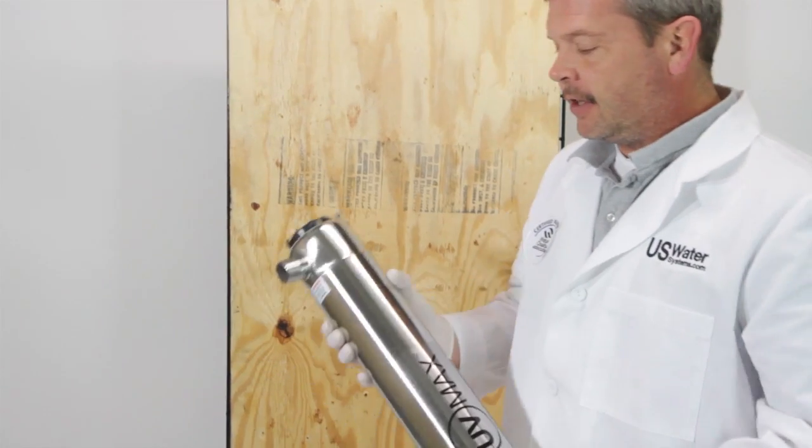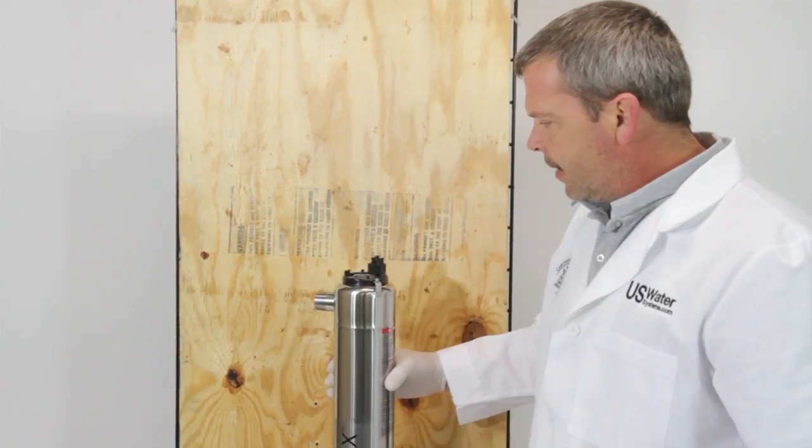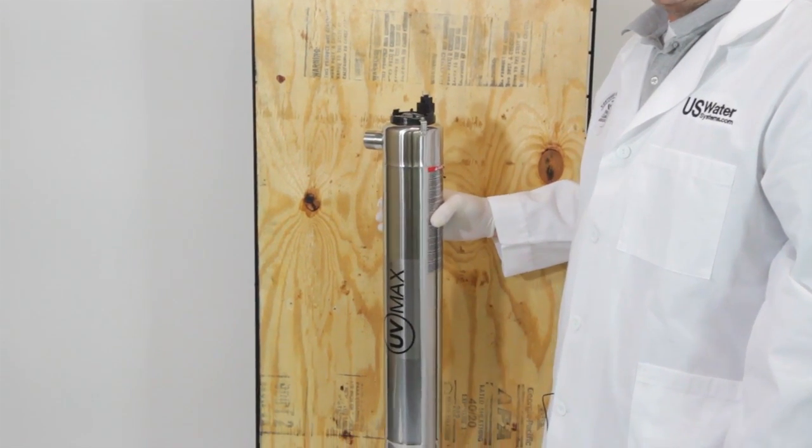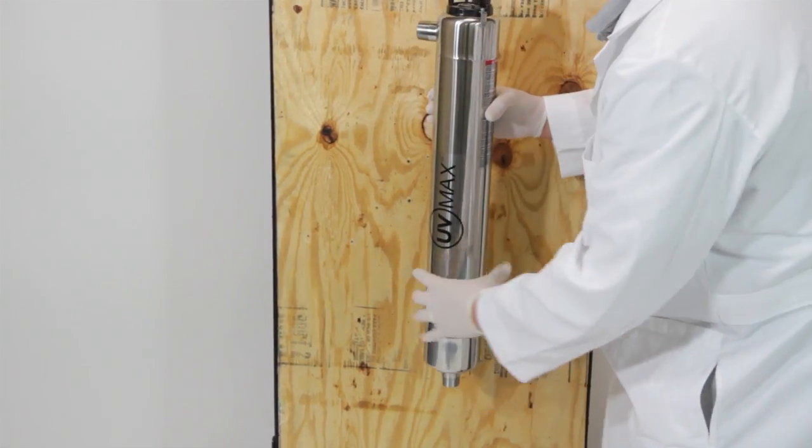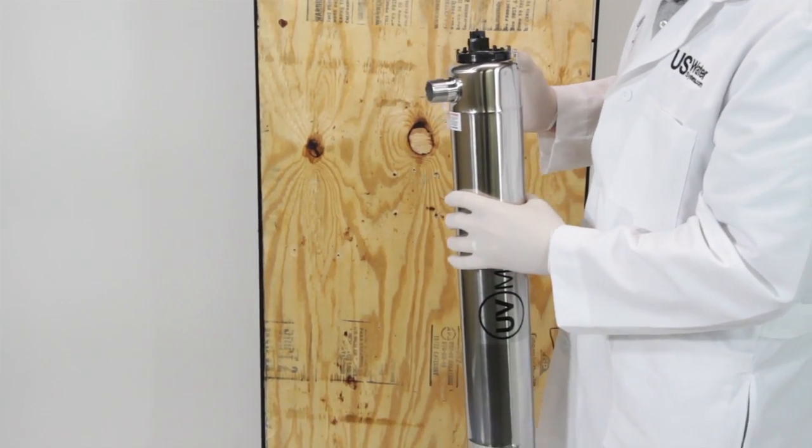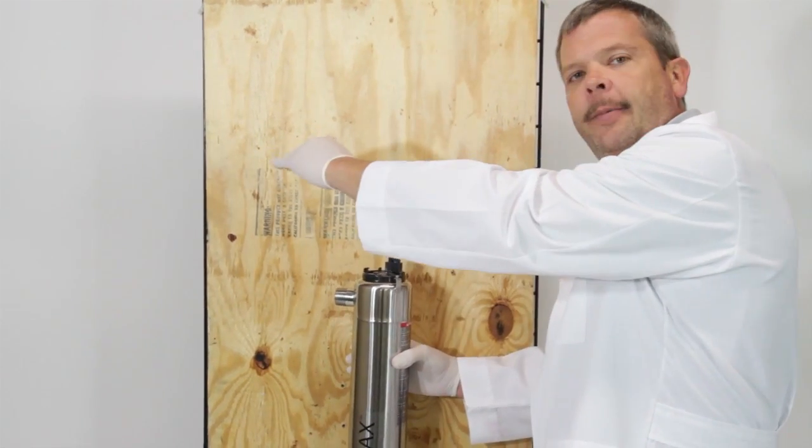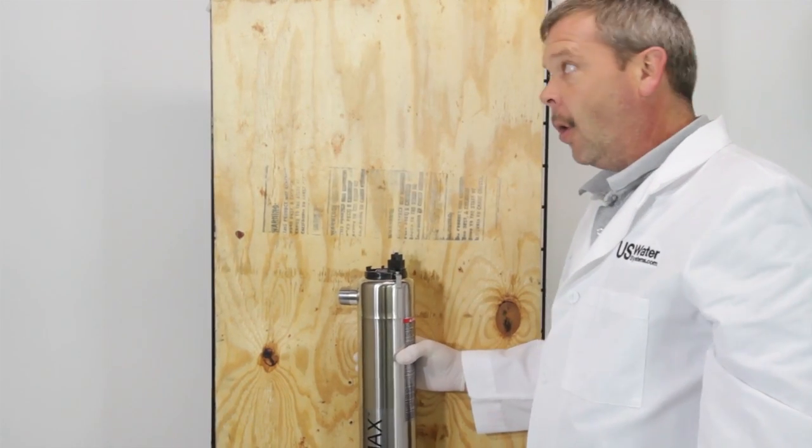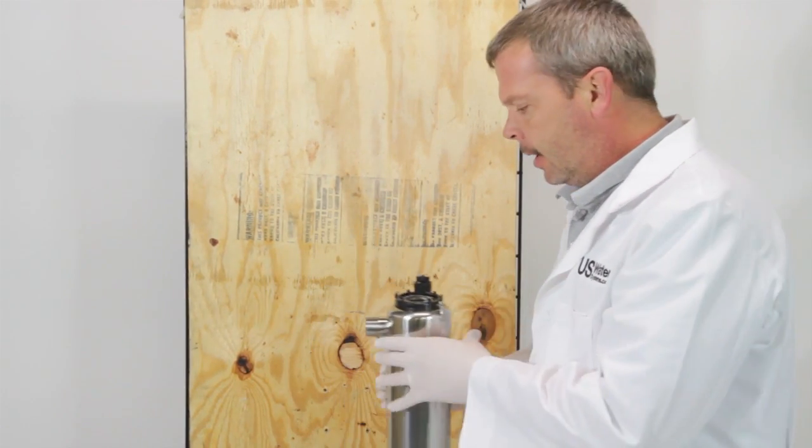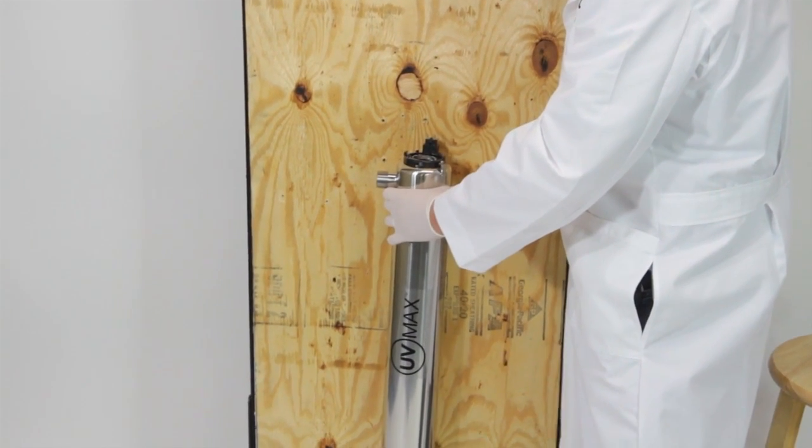First and foremost we're going to mount the chamber. When you mount the chamber, you want to keep a couple things in mind. If you're going to mount it vertical or horizontal, either way will work. We prefer vertical so that the water comes in from the bottom, swirls around, and comes out the top at the side. You're going to have to replace this bulb once a year or every 9,000 hours, so you don't want to put anything over the top where you can't slide the bulb back out. Typically we mount these lower to the ground in a vertical position.